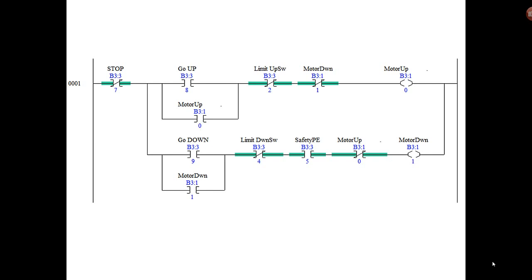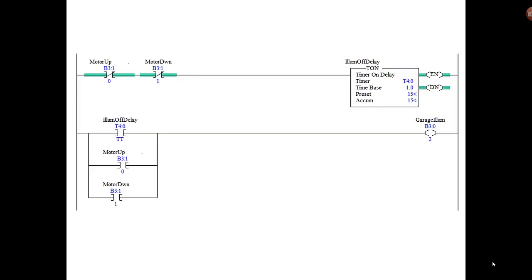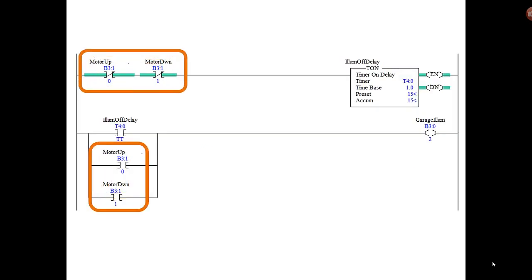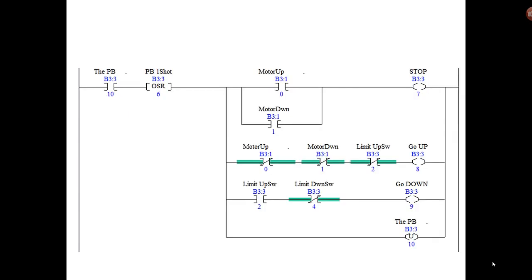So we replace every place where there was the control relay up and control relay down with motor up and motor down. And we're still not done here. We have a couple more that we have to replace because neither up or down were being used to start our timer and to provide garage lights, so make sure you replace them there as well.